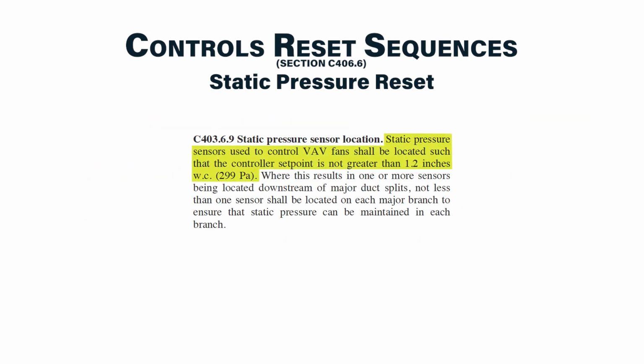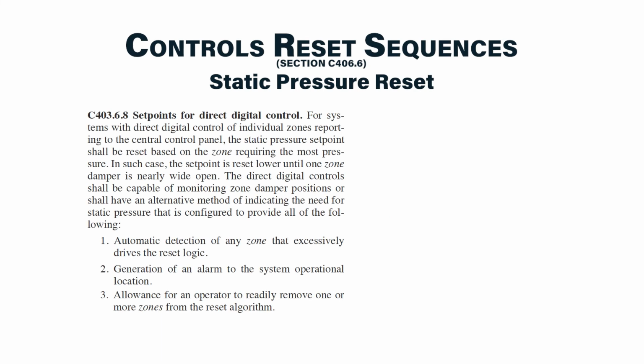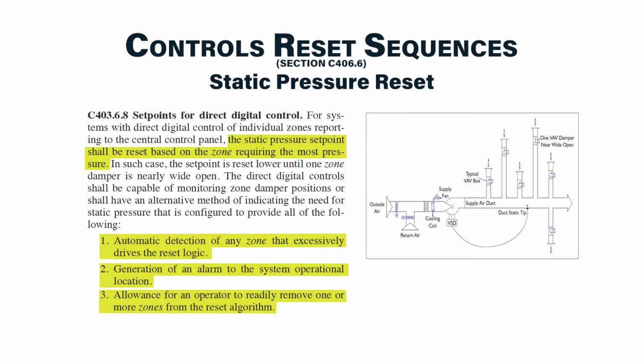C403.6.9 gives a requirement for where the pressure sensor needs to be located so that the static pressure isn't too high. The 2018 code then outlines requirements to reset the static pressure based on the zone that requires the most pressure. It also requires a way to alarm if there's a rogue zone that is driving the pressure too high while all the other zones are satisfied. This is a much more complicated sequence, and again, ASHRAE Guideline 36 will have a pre-written specification for this sequence.